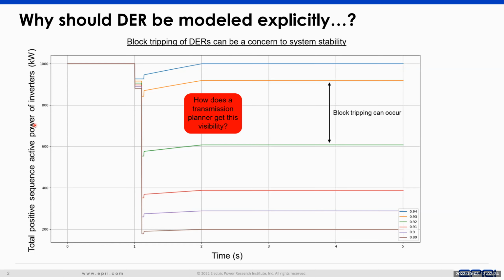But when that 200 kilowatts starts becoming close to, say, 1 or 1.5 megawatts, it becomes a large fraction of the load, and then it becomes important for the transmission planner to study this. If you assume this amount of DER exists at each bus or substation on a gigawatt-size network, things start to change.